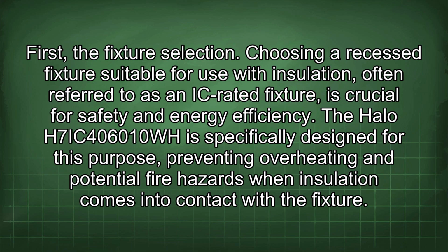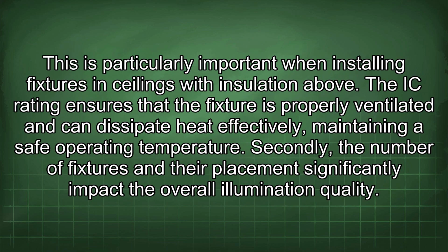To elaborate on these points, let's consider each aspect in more detail. First, the fixture selection. Choosing a recessed fixture suitable for use with insulation, often referred to as an IC-rated fixture, is crucial for safety and energy efficiency. The Halo H7IC 406010WH is specifically designed for this purpose, preventing overheating and potential fire hazards when insulation comes into contact with the fixture. This is particularly important when installing fixtures in ceilings with insulation above. The IC rating ensures that the fixture is properly ventilated and can dissipate heat effectively, maintaining a safe operating temperature.